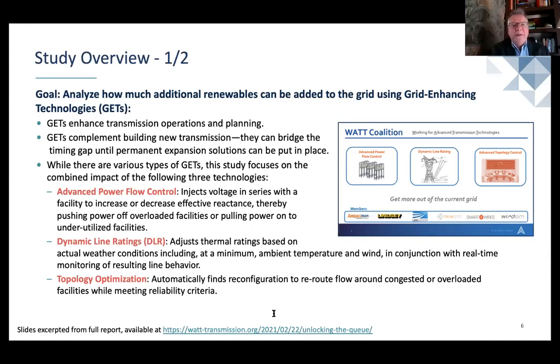So they added a transformer that would actually shift the impedance of the power system and force the flows off of the underlying 138 kV system to get them back up onto the 345 kV system where there's much more capacity. Advanced power flow controllers are very similar.